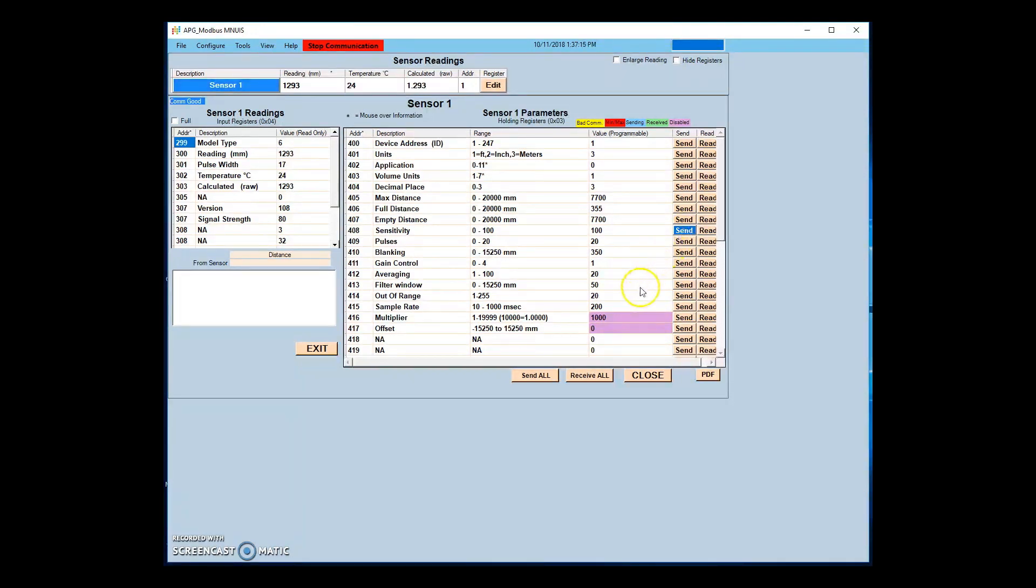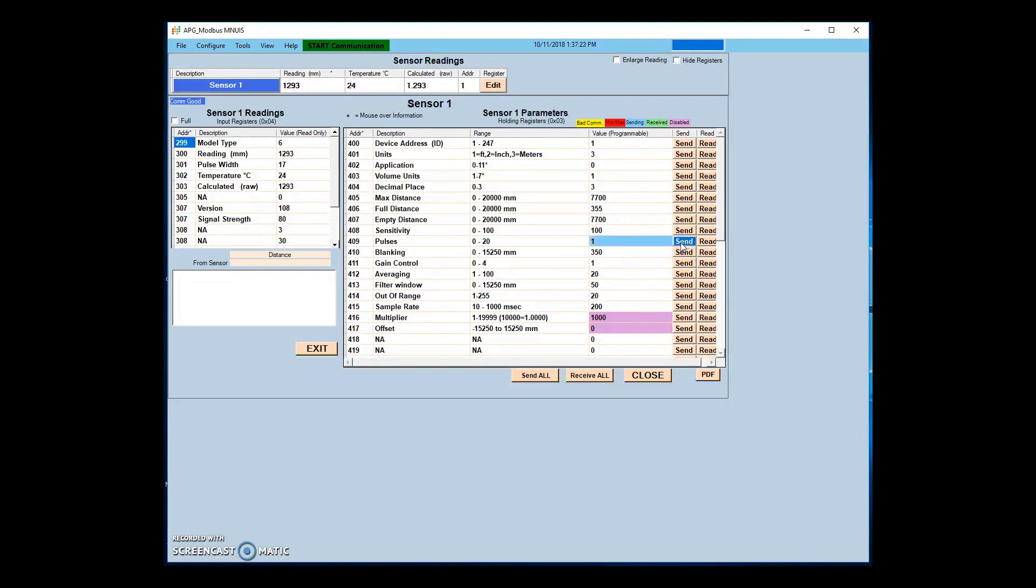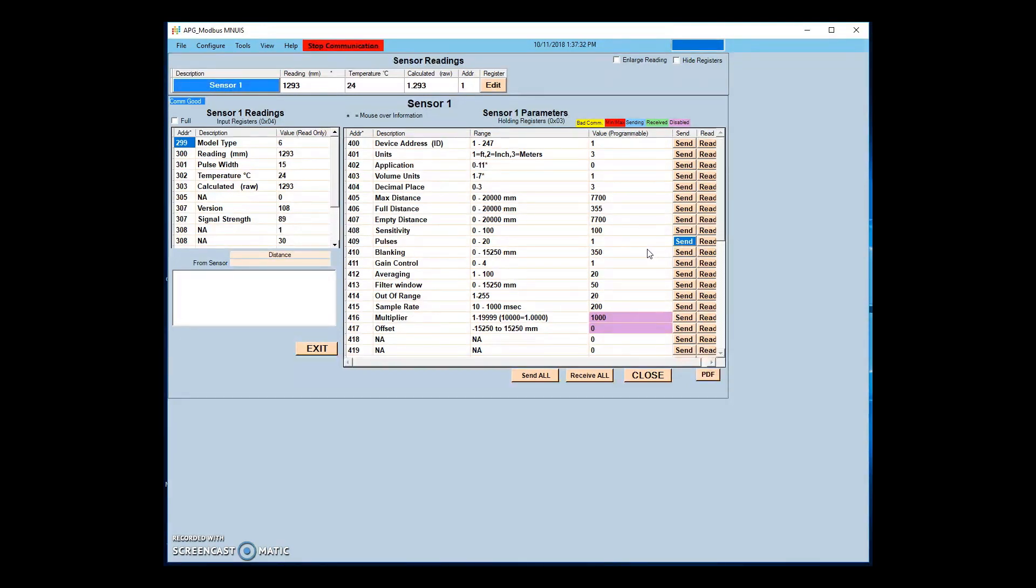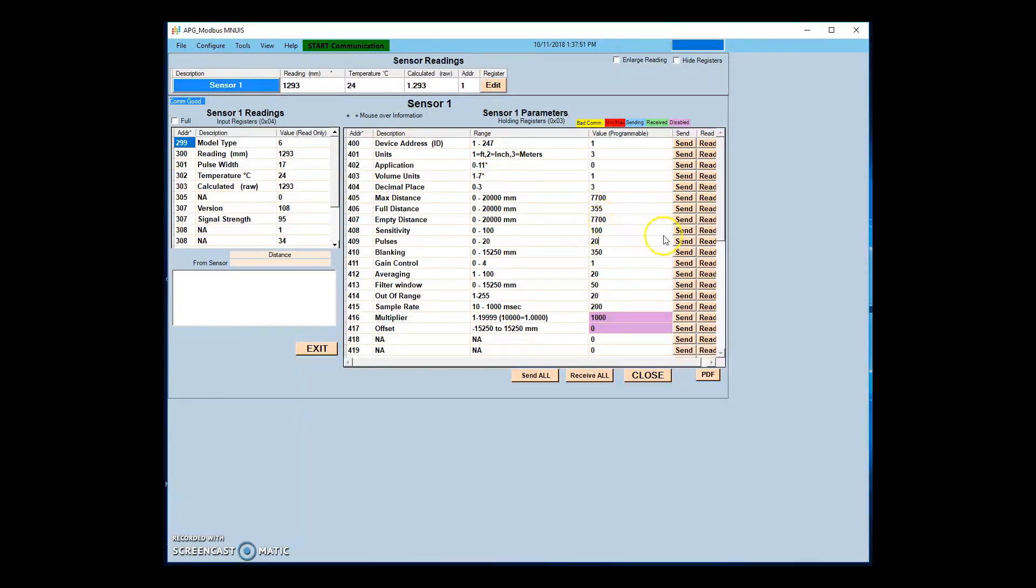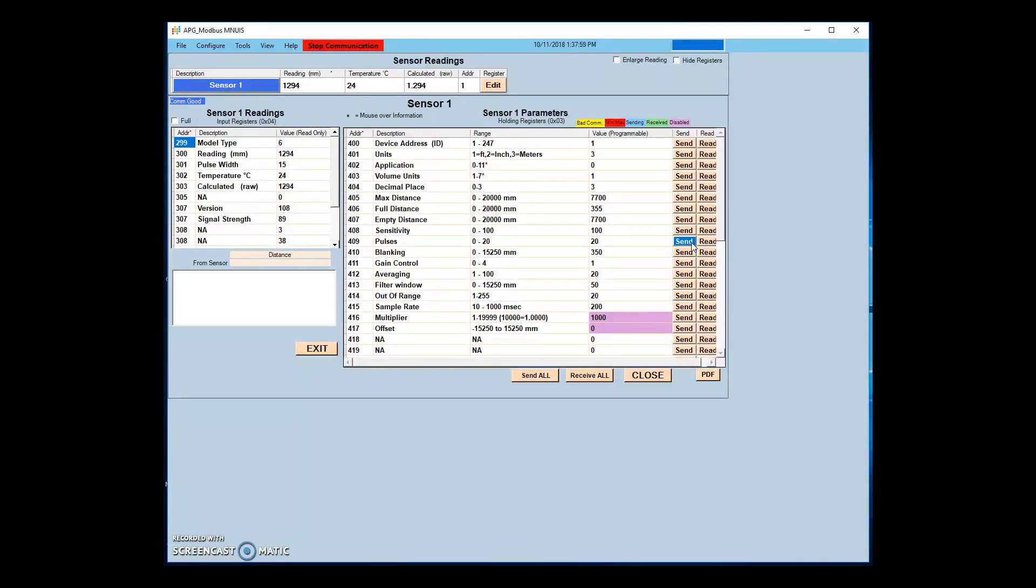The pulses parameter sets the number of ultrasonic pulses per transmission. More pulses will result in a stronger echo being returned to the sensor. In AutoSense, HardTarget, or SoftTarget modes, this parameter will set the maximum pulses allowed to be sent. In Manual mode, this value will set the number of pulses. Increasing pulses will create stronger signals in damping environments. In acoustically active environments or enclosed areas, the amount of pulses can be decreased to reduce multiple echoes.